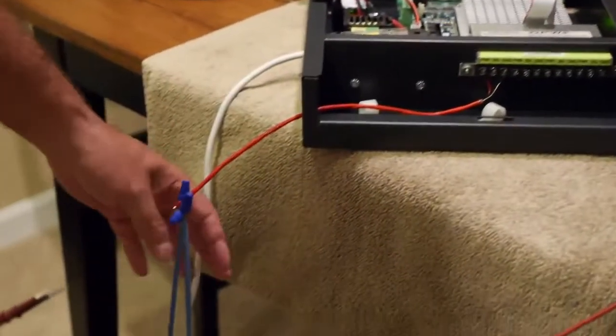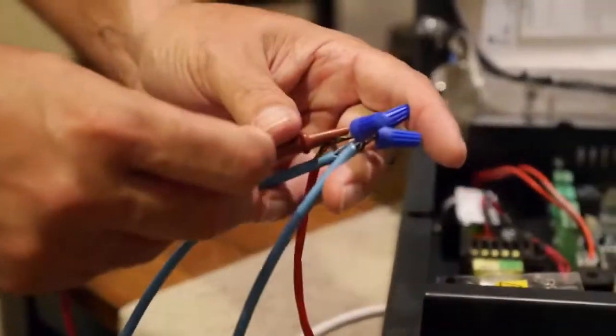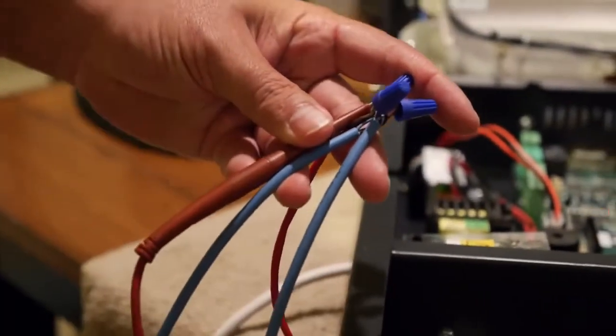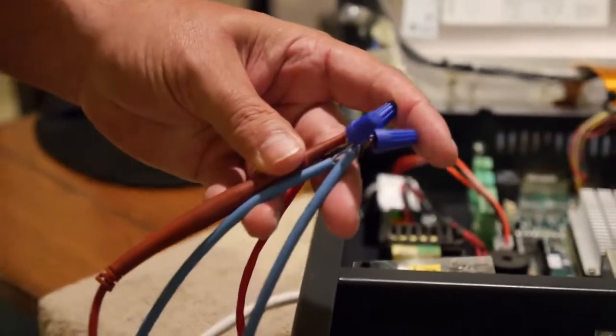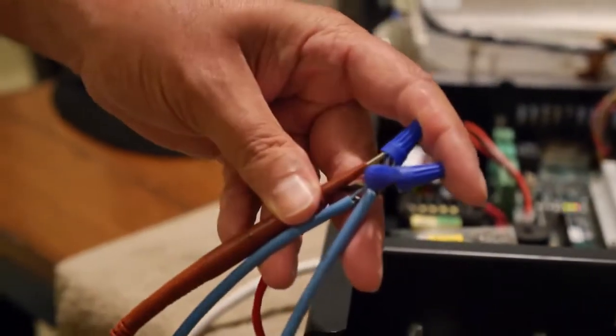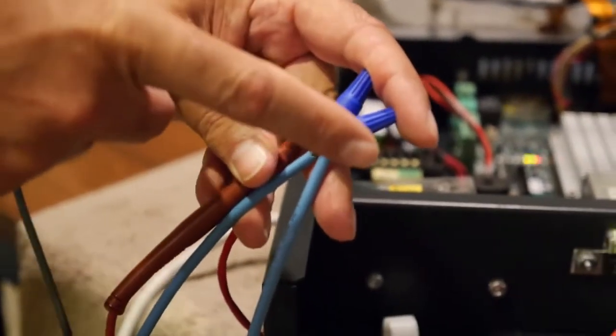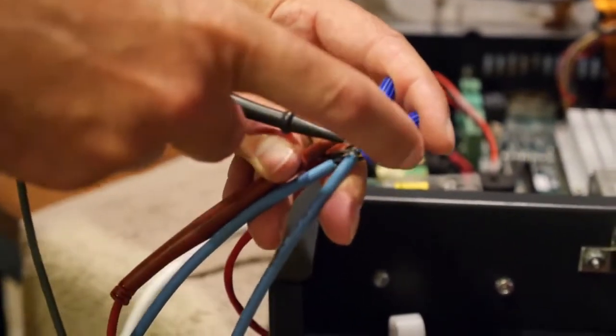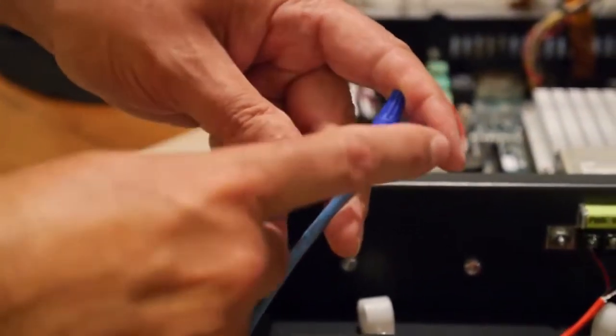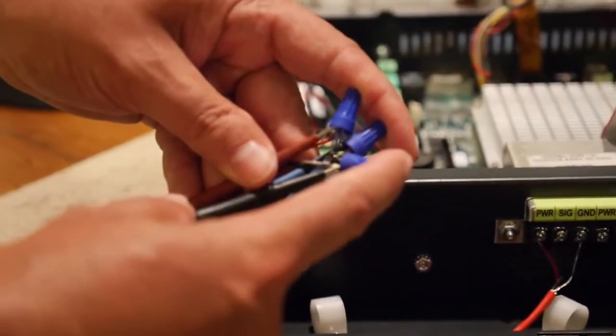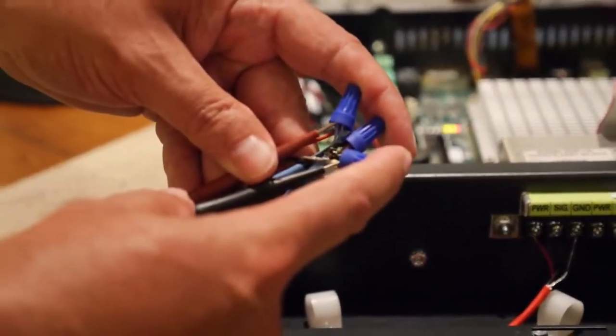The next thing you want to do is come back out to the field. You know that the red wire is your power wire, and then the shield is the ground. Read voltage out in the field to make sure that you still have voltage coming from the wire and that it's not broken, and that you have the exact same voltage from the barrier that you do on the end of the wire.